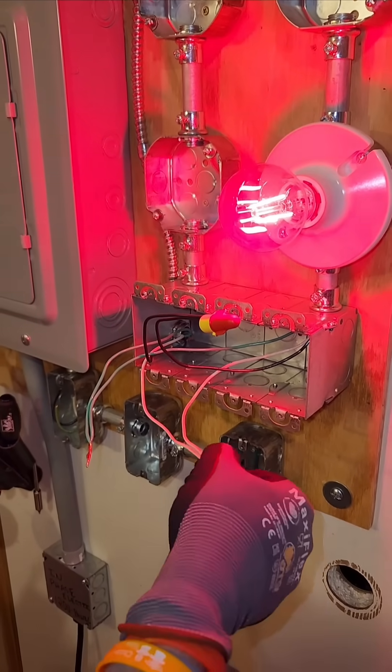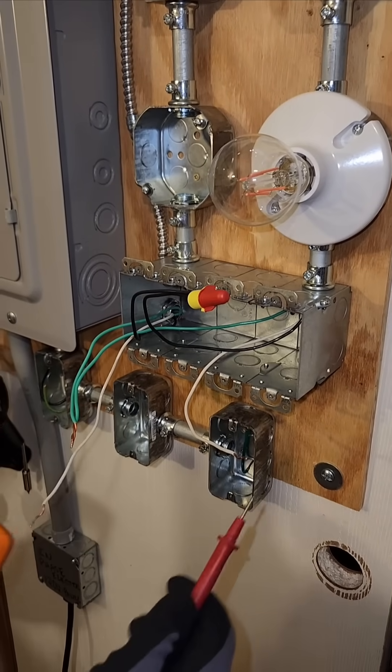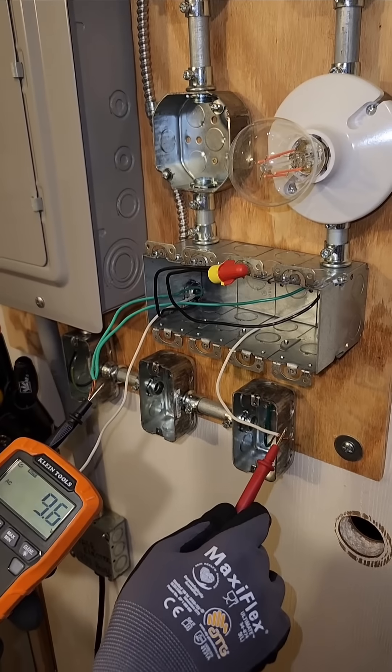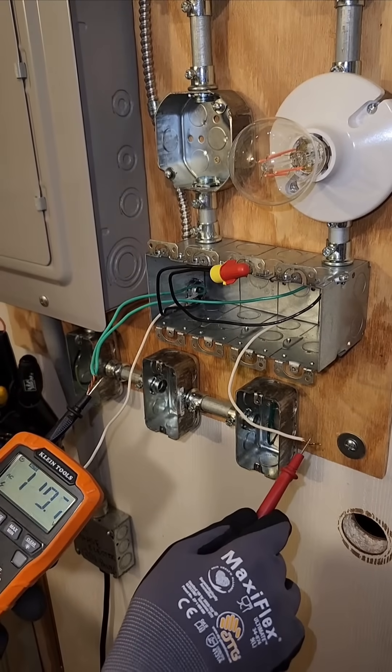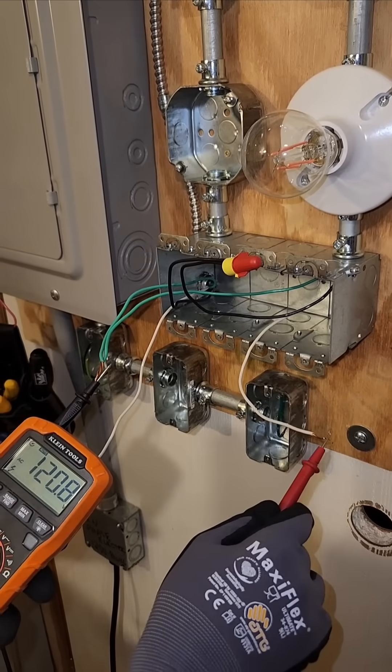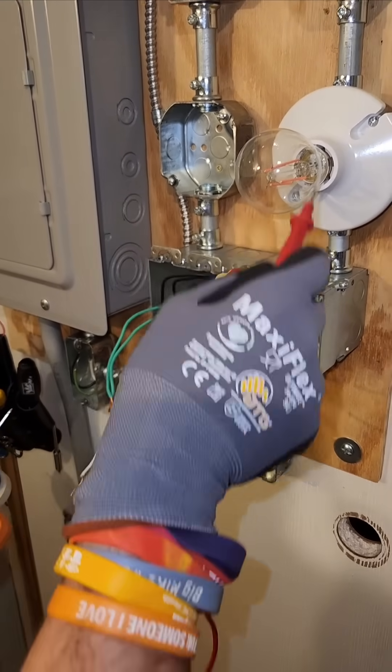But now let's break this neutral connection. Now what we're going to find is that we have 120 volt potential between this white and this green. So now we have 120 volt potential relative to ground off of the white wire that's coming off of the light bulb.